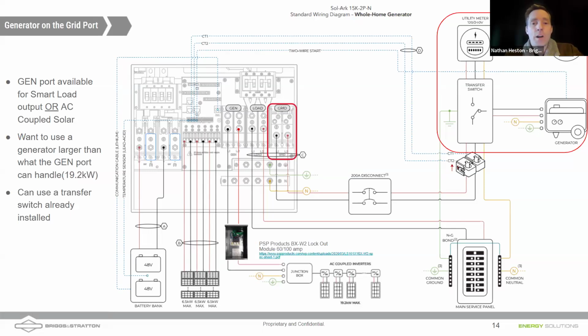But essentially that will disconnect your AC coupled solar to prevent backfeeding of a generator. I'm a big fan of leaving that generator port open, or using that for AC coupled solar in a retrofit, and making these extra efforts to make sure we're not backfeeding the generator.